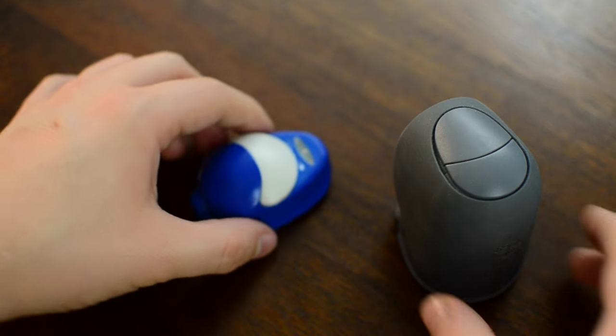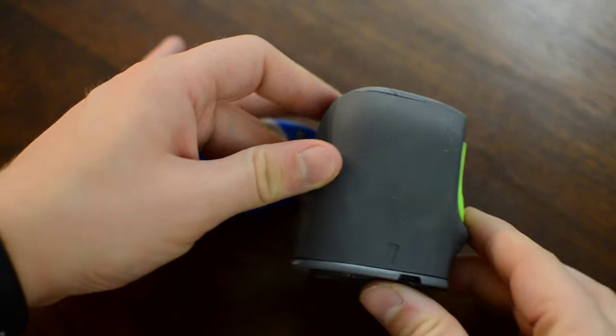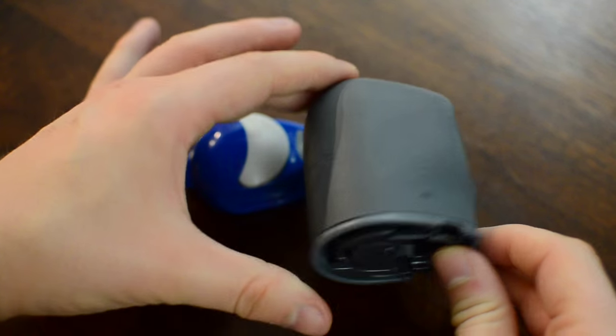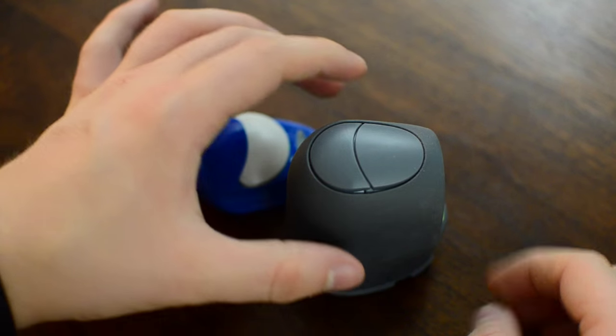And that does make the sensor go straight in, compared to the Enlite sensor here, or the G4 sensor, which is at an angle. So the Enlite sensor is straight in, a 90 degree angle, whereas the Dexcom G4 is at an angle.